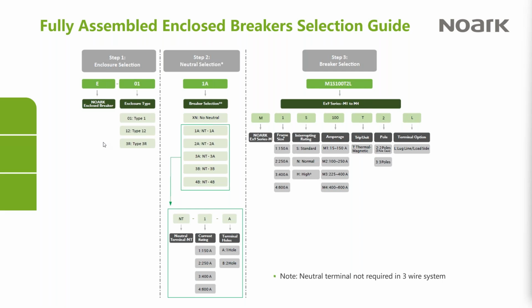So when you require a neutral, the neutrals are designed to match the maximum frame rating of each frame. A 1A neutral is made to go with an M1 breaker up to 150 amps. And you can see in the table at the bottom the selection details for the neutrals. A 1 is 150, a 2 is 250, and of course they align completely with the M1 and M2 breakers. Then you'll see the final digit, the A or the B, indicates whether the lugs on the neutral have a single conductor opening or a 2-conductor opening. And that's meant to match up to what the breaker has. Same with the M4. It has a single option available for the neutral selection.